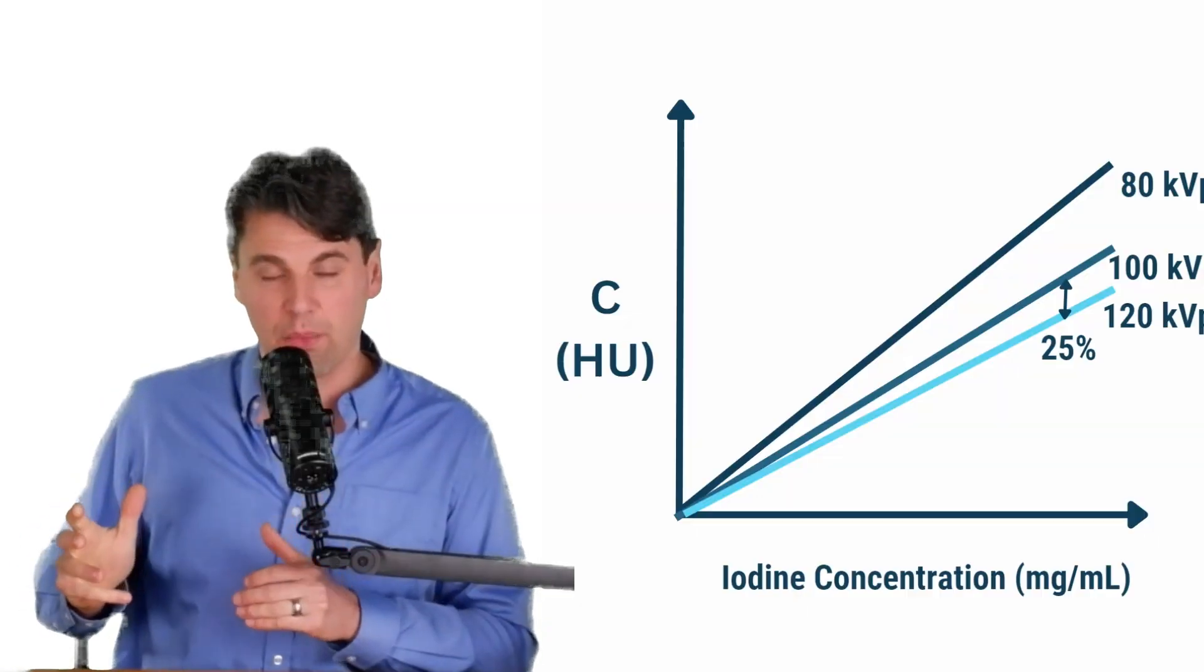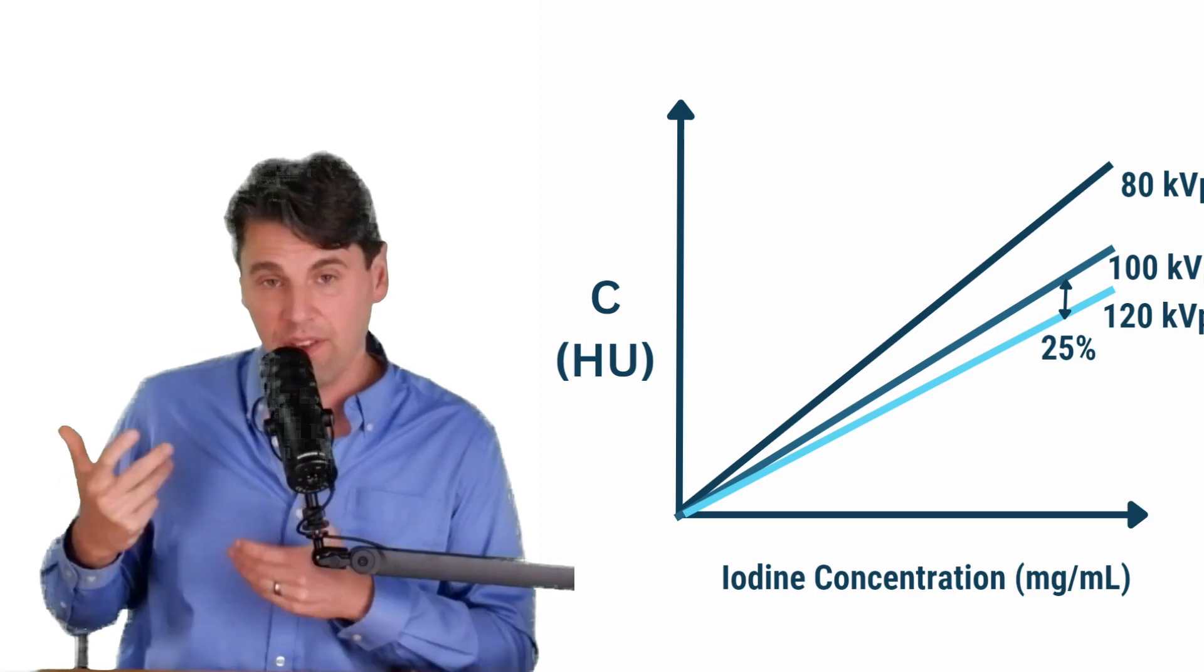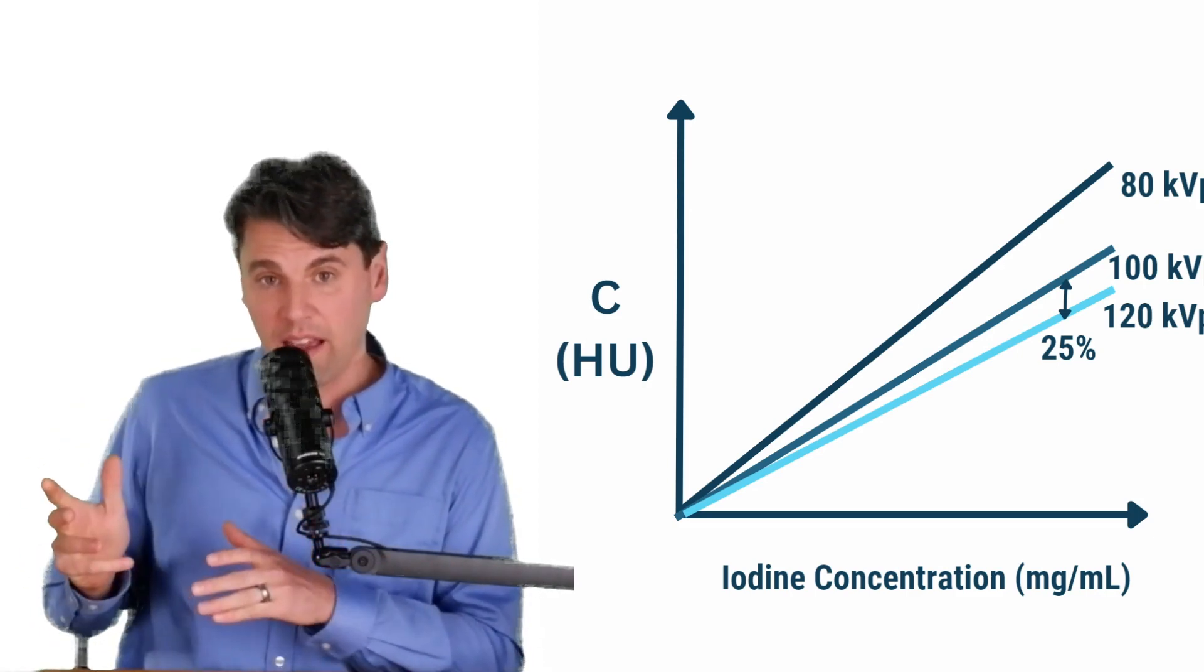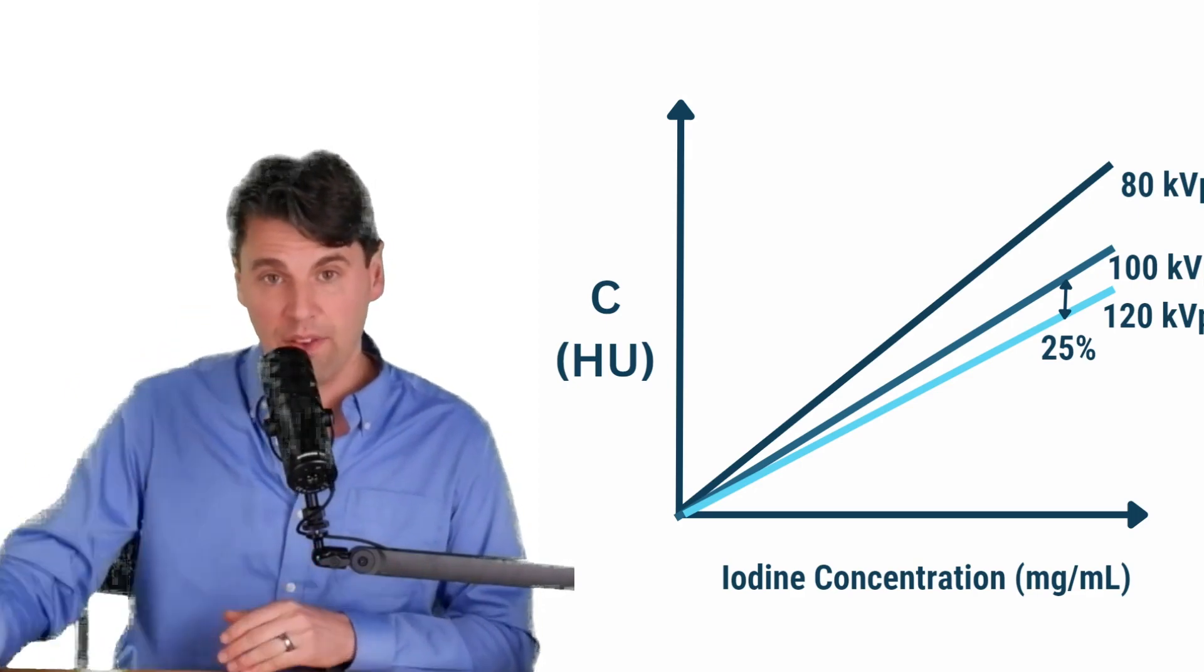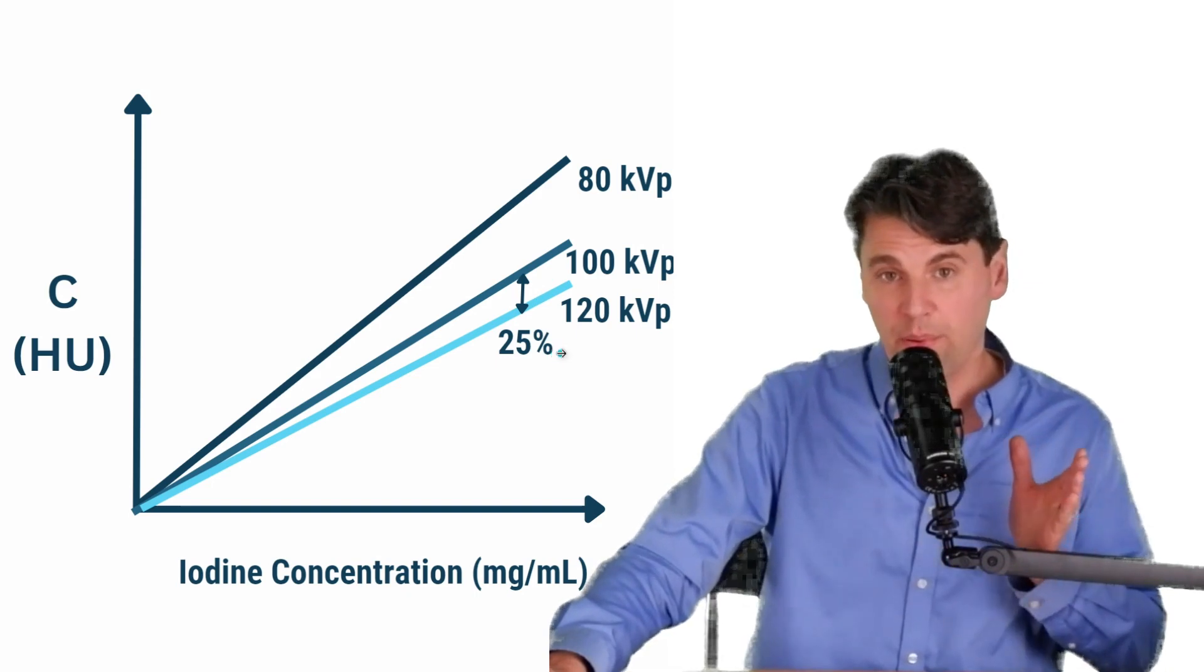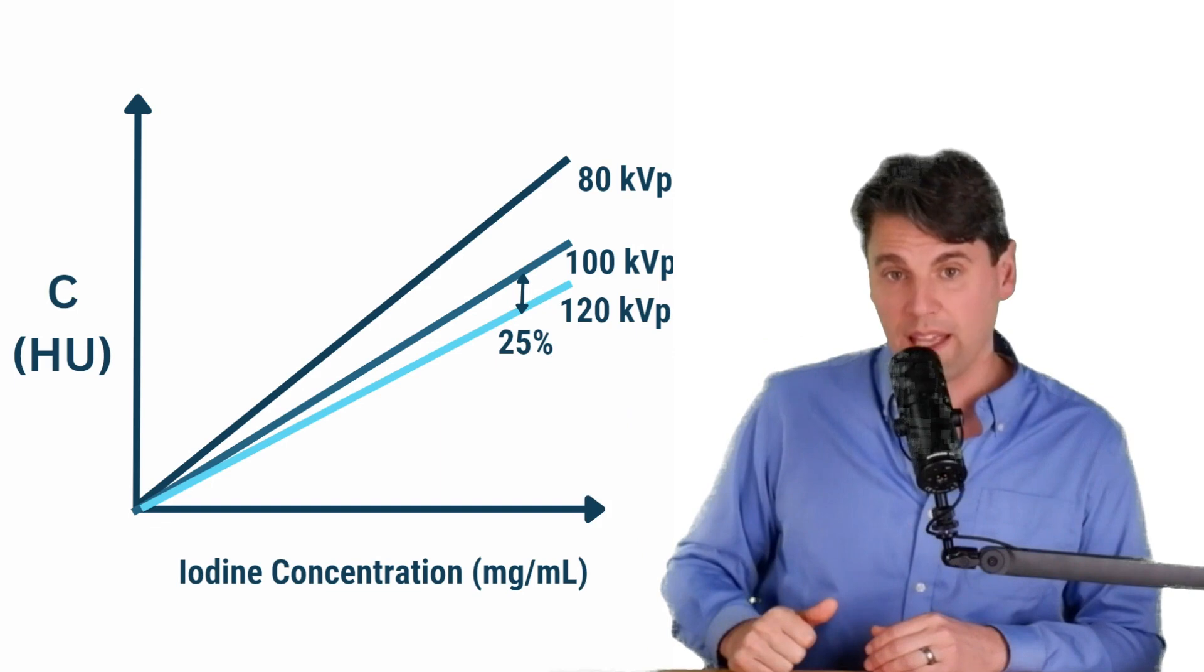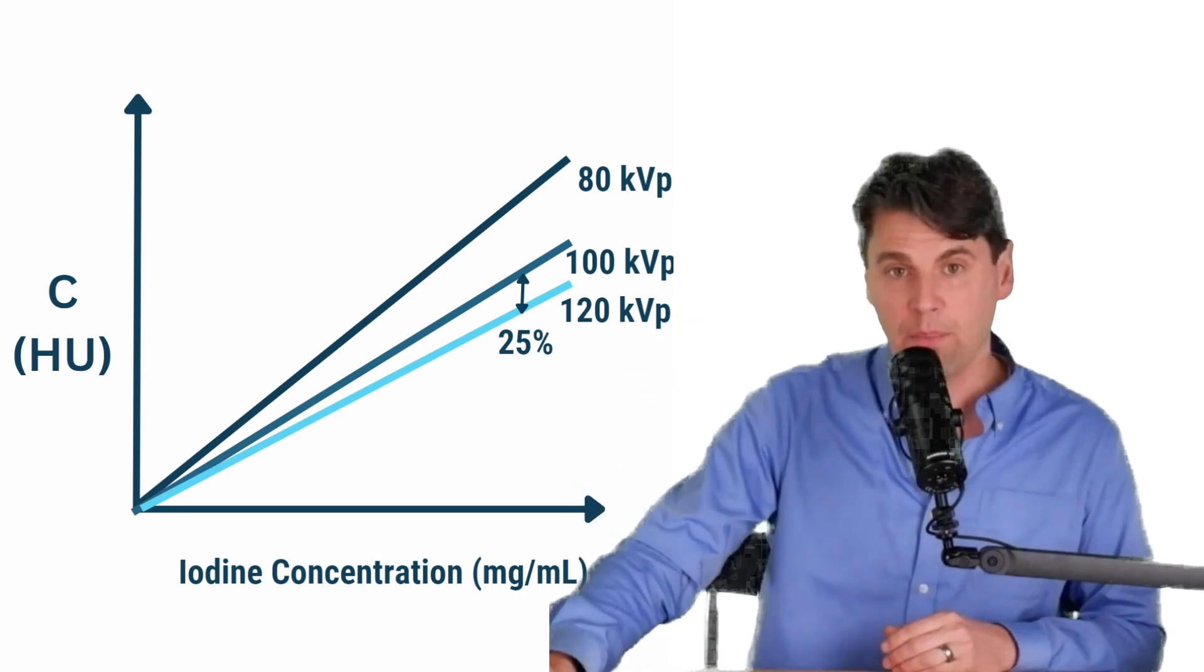As far as the contrast term, we've talked a lot before in our previous videos on the KVP relationship, especially for a photoelectric contrast, how there's really a steep increase for the lower KVPs. So you can get more contrast going to those lower KVPs. It's usually around 25% more contrast, and making a jump of 20 KVP to a lower KVP, you're going to be getting significantly more contrast.